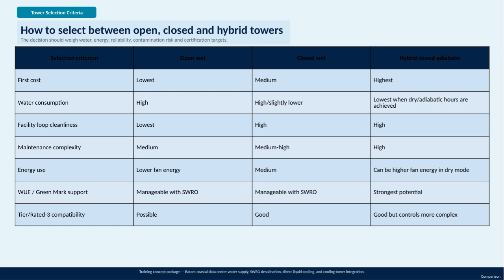Closed wet towers offer better loop cleanliness and are good for Tier 3 ratings, though their first cost and maintenance needs are slightly higher. Hybrid closed adiabatic towers have the highest upfront cost and maintenance complexity, but they excel in minimizing water consumption during dry or adiabatic periods, provide excellent loop cleanliness, and have strong potential to support green certification like the Green Mark. However, energy use can be higher due to increased fan energy in dry mode, and controls are more complex. This comparison is essential when planning coastal data centers, such as in Batam, where integration with seawater reverse osmosis desalination and direct liquid cooling systems must be carefully balanced for optimal performance and sustainability.